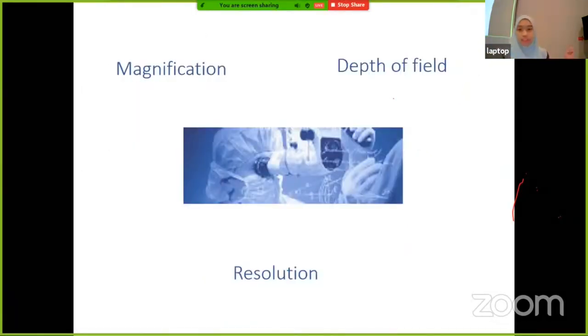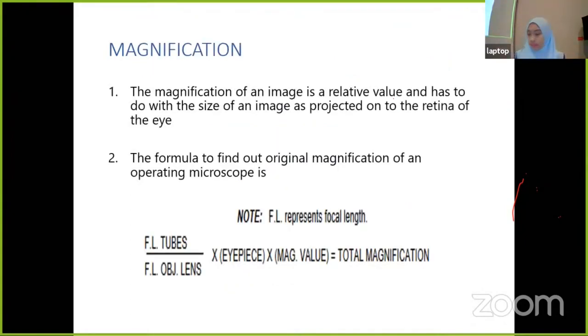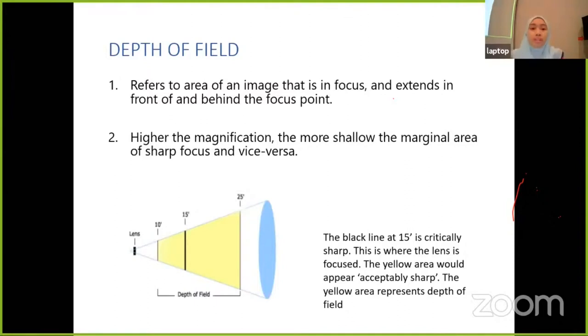I will now talk briefly about magnification, depth of field, and resolution of the operating microscope. Magnification of an image is a relative value and relates to the size of the image as projected onto the retina of the eye. The formula is: focal length of the tube divided by focal length of the objective lens, multiplied by the eyepiece magnification value — giving us the total magnification. Depth of field refers to the area of an image that is in focus and extends in front of and behind the focal point. The higher the magnification, the more shallow the area of sharp focus, and vice versa.